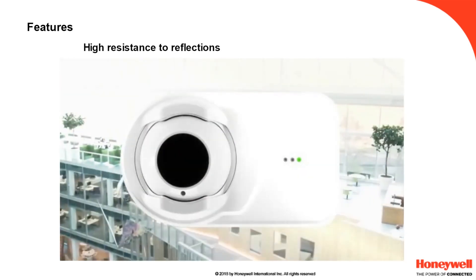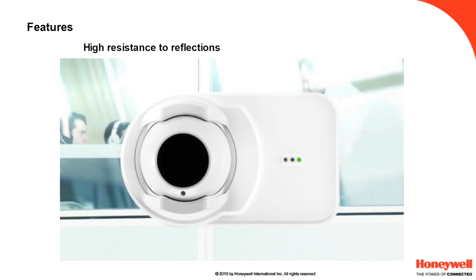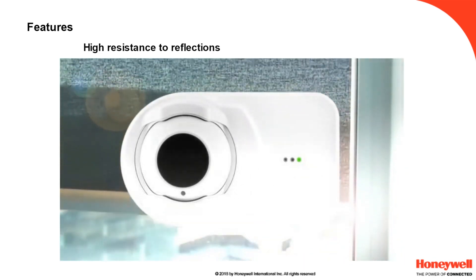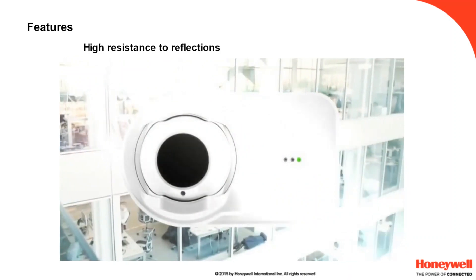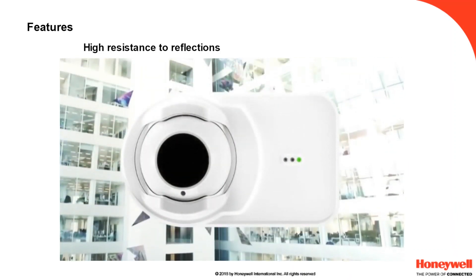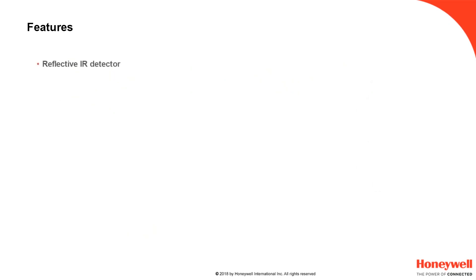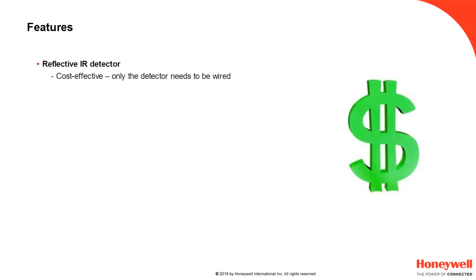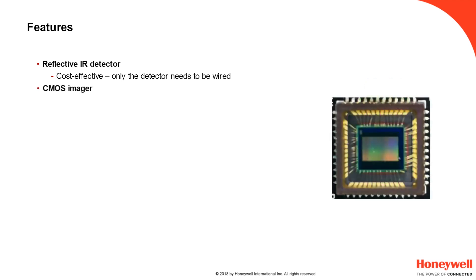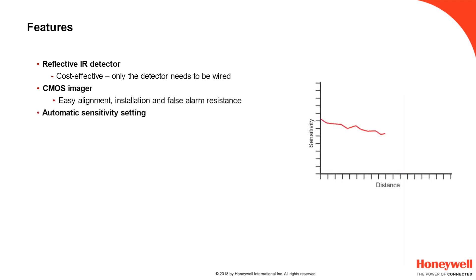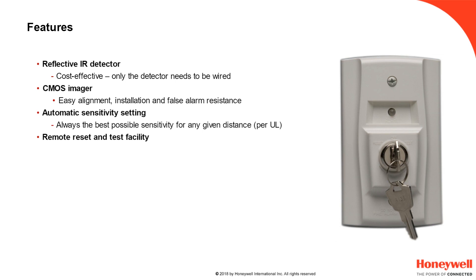This same feature means that reflections from modern building materials — glass and polished stainless steel for instance — will have no effect on the device. Features include: a reflective IR detector, cost-effective installation (only the detector needs to be wired in), a CMOS imager for easy alignment and false alarm resistance, automatic sensitivity settings providing the best possible sensitivity for any given distance per UL requirements, remote test and reset facilities, electronic smoke test, and compatibility with the RTS151 key.